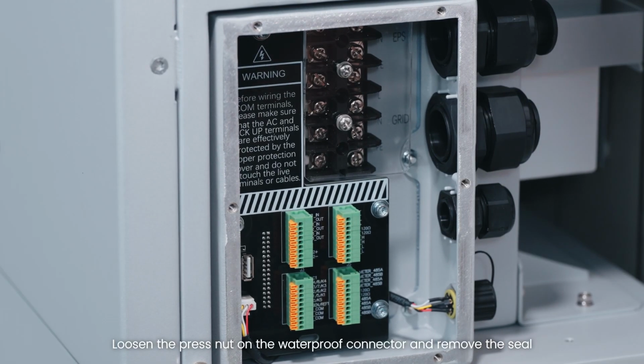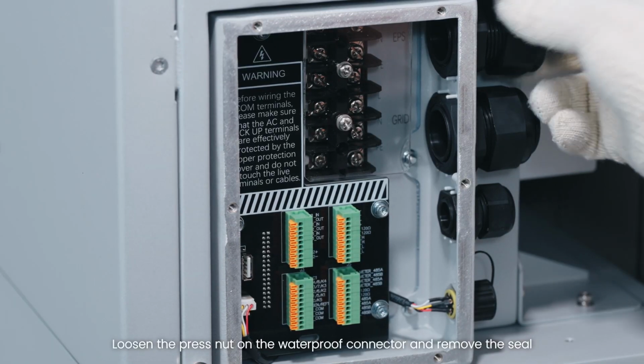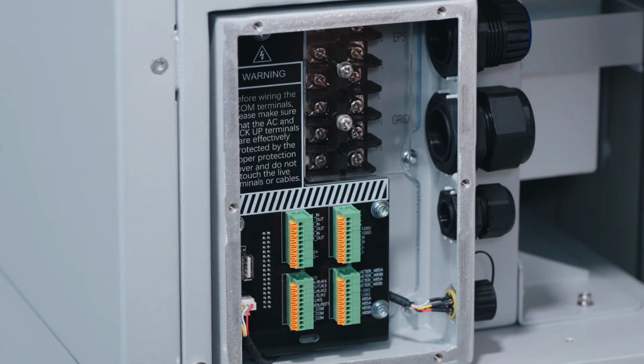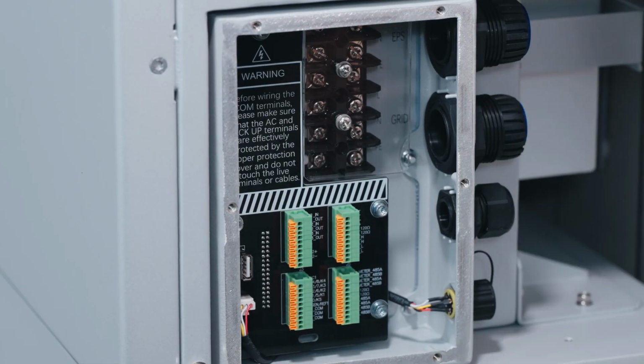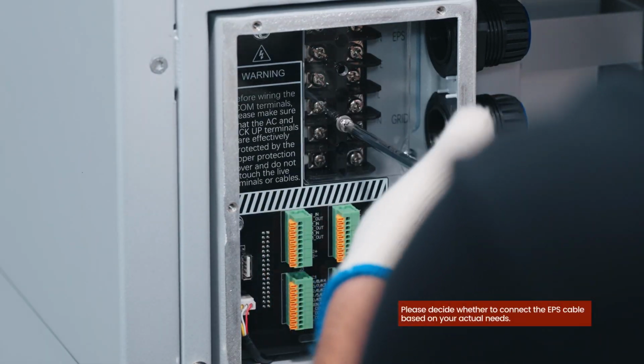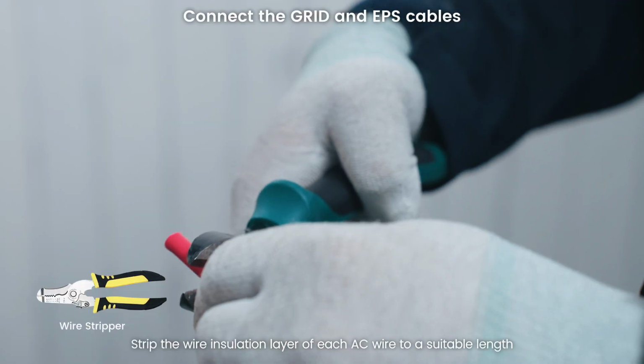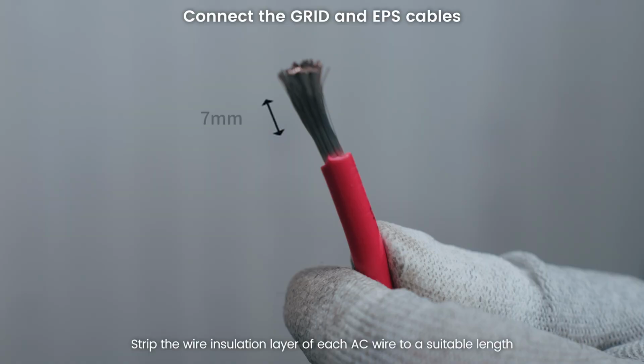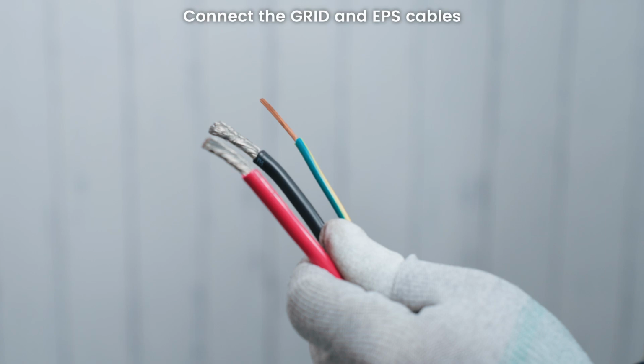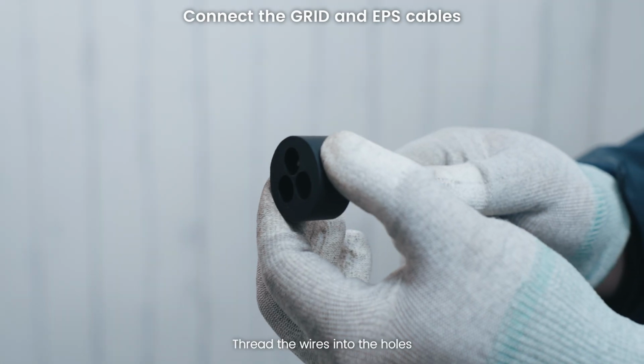Loosen the press nut on the waterproof connector and remove the seal. Strip the wire insulation layer of each AC wire to a suitable length. Thread the wires into the holes.